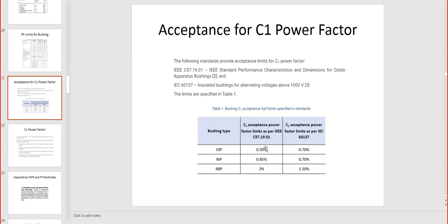Usually what you can do when you see something like this, you can take the most stringent, the one that is asking for the lower value, and then you are safe. Like, you know, IEEE with 0.5, and then for the next one, as opposed to take IEEE, you go to IEC and you say 0.7, and again you stay with the international for the last type, the RBP bushing type. It's just an excerpt from a longer table, so I didn't put here everything, so it's from the standards.